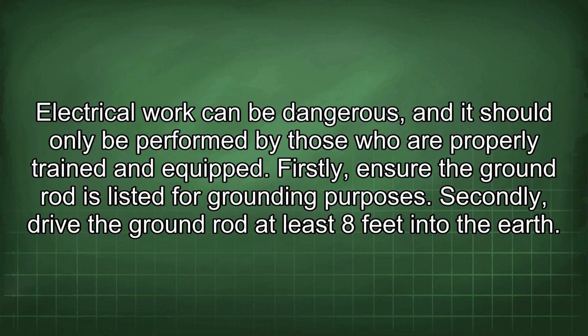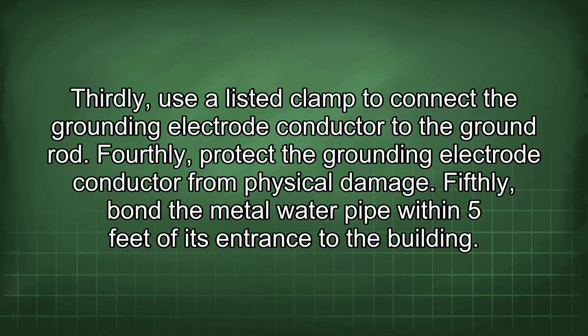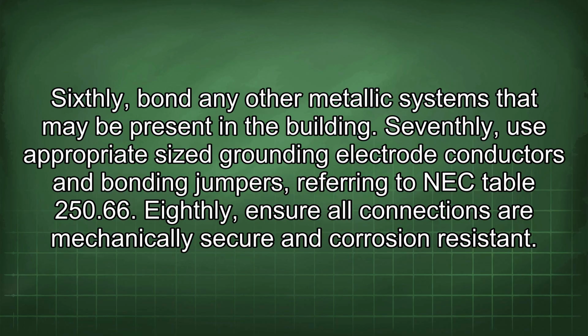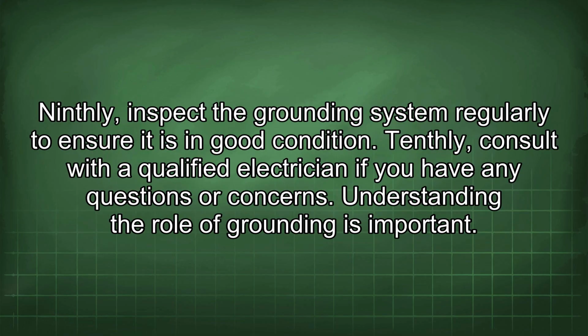Firstly, ensure the ground rod is listed for grounding purposes. Secondly, drive the ground rod at least 8 feet into the earth. Thirdly, use a listed clamp to connect the grounding electrode conductor to the ground rod. Fourthly, protect the grounding electrode conductor from physical damage. Fifthly, bond the metal water pipe within 5 feet of its entrance to the building. Sixthly, bond any other metallic systems that may be present in the building. Seventhly, use appropriately sized grounding electrode conductors and bonding jumpers, referring to NEC Table 250.66. Eighthly, ensure all connections are mechanically secure and corrosion resistant. Ninthly, inspect the grounding system regularly to ensure it is in good condition. Tenthly, consult with a qualified electrician if you have any questions or concerns.